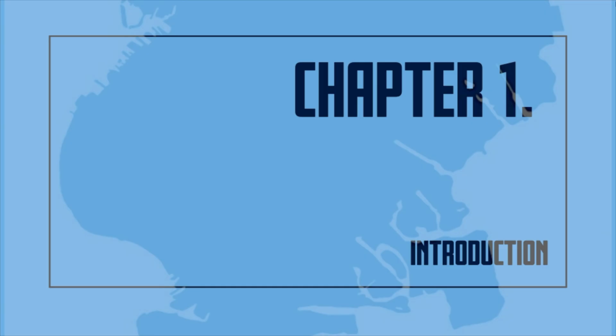Fire Code 901.4.1. Systems not complying with this section shall be considered to be impaired. It shall be unlawful to install or maintain any fire protection system or device that has the physical appearance of fire protection equipment but that does not perform a fire protection function where it may be confused with actual fire protection equipment. Fire Code 901.4.4. An example would be a closed-circuit television camera modeled to look similar to a sprinkler head.